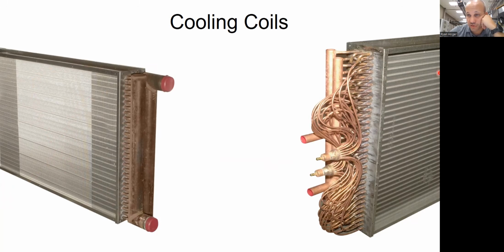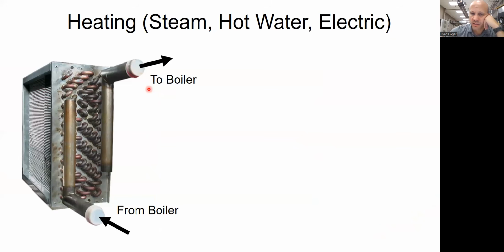And then those guys send refrigerant up and down, up and down, until they get back to these, in this case, 2 return headers. So if you see this spaghetti-looking set of copper piping here, it's a DX system, which means we can get a heat pump version for that. And if it's this kind of distribution, and when you open the door to the air handler it's a chilled water system, we're not talking about that today. That's Module 5. Any questions on those?